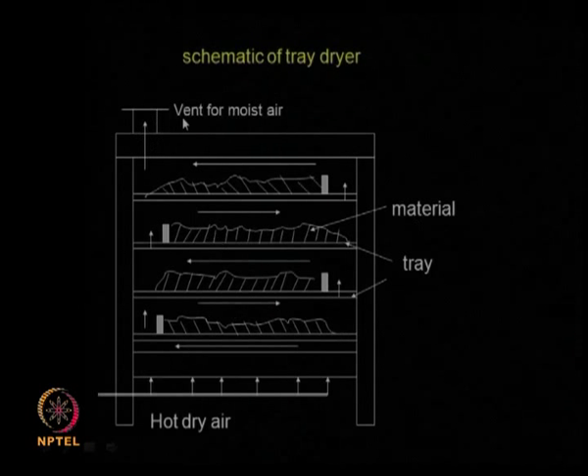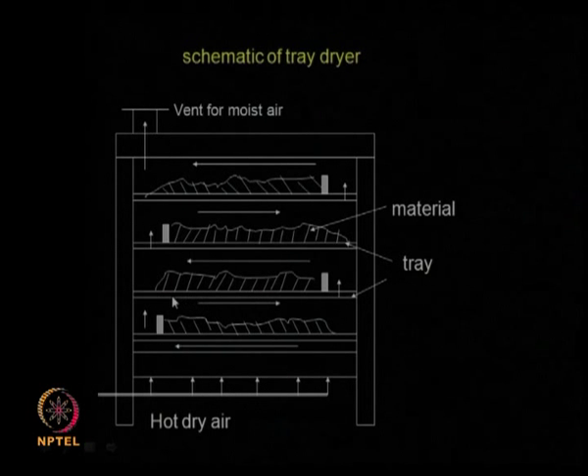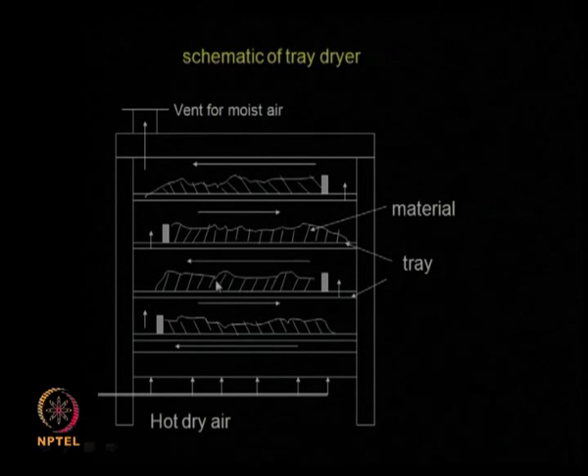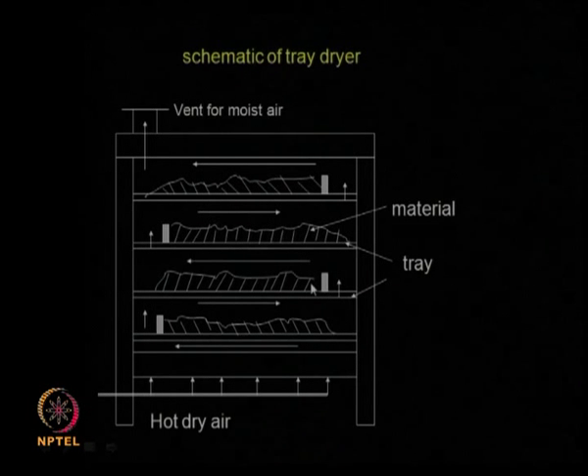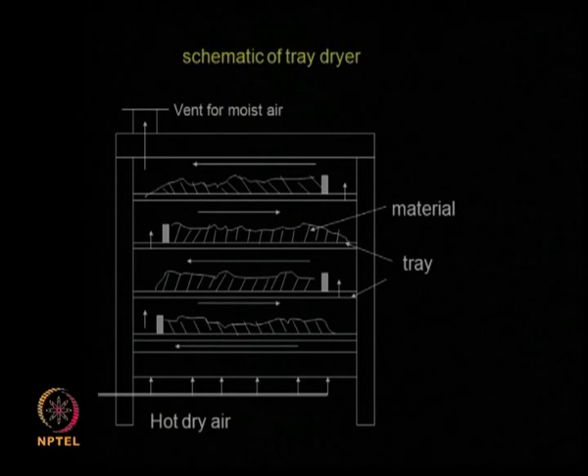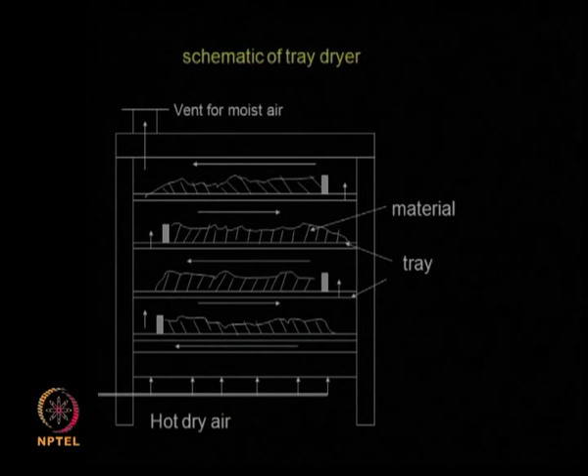In a typical air tray dryer, hot air comes from the bottom — heated by an external electrical heater or hot water, with a dehumidifier. This air comes in contact with the solid material placed on trays, travels through the porous solid material carrying moisture and drying it, then is vented out on the other side where a condenser can collect the moisture or solvent. This is a batch operation: once drying is done, you remove all trays and the solid material, repack with wet solid, and restart the process. Loading and unloading can take quite a lot of time.